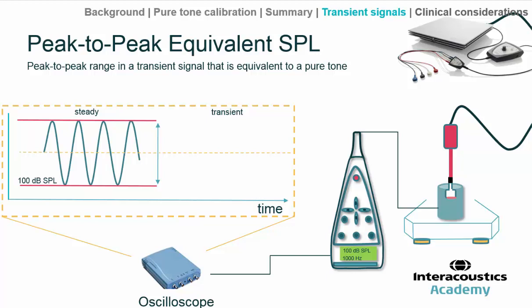That steady-state information from the pure tone, which can be both visualized on the oscilloscope and captured accurately by the sound level meter, can then be compared to a transient that can be captured electro-acoustically by the oscilloscope but not measured accurately by the sound level meter. For example, we might take a chirp, ignore any information on the screen of the sound level meter, look at the electro-acoustic transient on the oscilloscope, and increase the level until we match it to the peak-to-peak voltage of the known reference level — giving us a chirp calibrated to 100 dB peak-equivalent SPL.